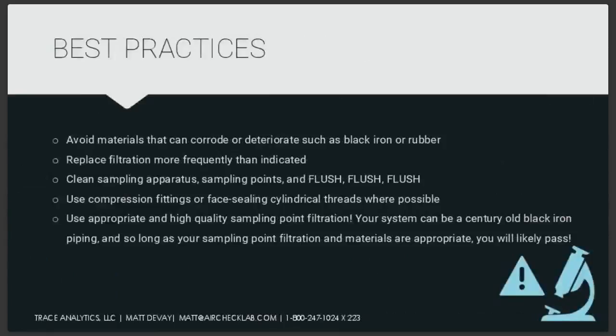Avoid materials that can corrode or deteriorate, like black iron or rubber. One of my first days on the job here, I got a picture of a sampling point, and the entire thing was probably 20 or 30-year-old rusting out black iron, and we're failing our particles. Well, that's probably because you're using rusting black iron as your point of use material. Replace your filtration more frequently than indicated. You don't want to wait until it's a problem to replace these filters. And spend a little bit extra money on that filter. You're going to save yourself a lot of headache further down the line.